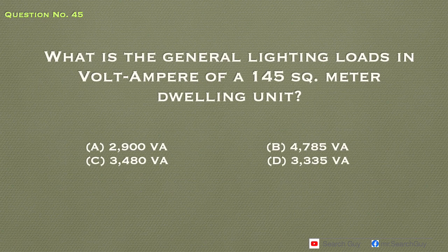Question number 45. What is the general lighting loads, in volt-ampere, of a 145 square meter dwelling unit? A. 2,900 volt-amperes, B. 4,785 volt-amperes, C. 3,480 volt-amperes, D. 3,335 volt-amperes. Answer: C. 3,480 volt-amperes.